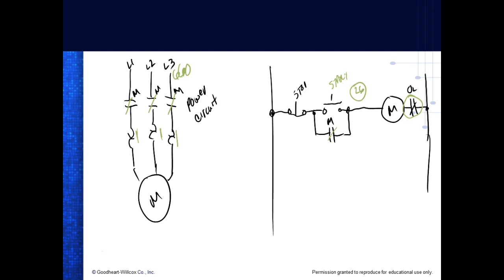Now we have no overloads in a PLC program, so you'll have to take care of this out in your control circuit, right? You understand? Your PLC is not going to run a motor normally. It's going to have to be a little tiny thing, like a fractional horsepower motor. So my little motors over here are these 24-volt motors. The PLC can run it, but the PLC cannot run a three-phase motor. But what can the PLC do? Pick up that guy, right? So we would hook this up to an outlet, and then that guy would run it. But then we would take care of the overloads out there.